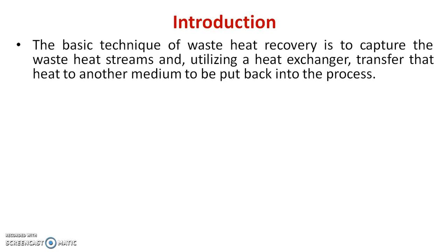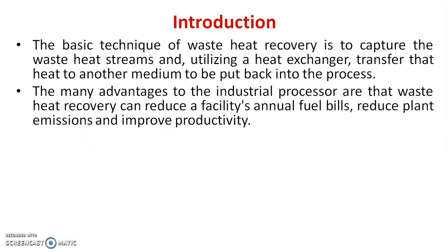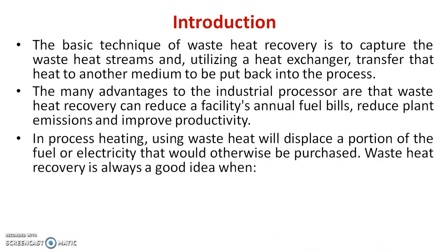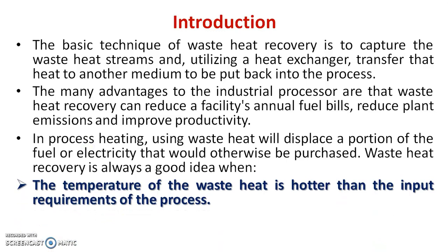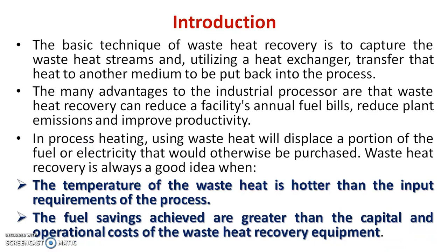The basic technique of waste heat recovery is to capture the waste heat streams and, utilizing a heat exchanger, transfer that heat to another medium to be put back into the process. The many advantages to the industrial processor are that waste heat recovery can reduce a facility's annual fuel bills, reduce plant emissions, and improve productivity. In process heating, using waste heat will displace a portion of the fuel or electricity that would otherwise be purchased. Waste heat recovery is always a good idea when, number 1, the temperature of the waste is hotter than the input requirement of the process, and number 2, the fuel savings achieved are greater than the capital and operational cost of the waste heat recovery equipment.